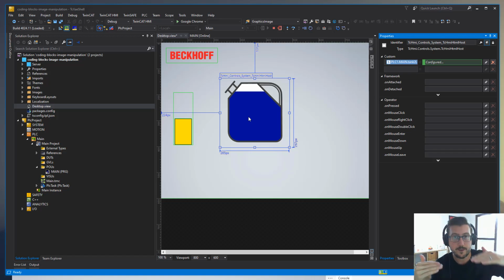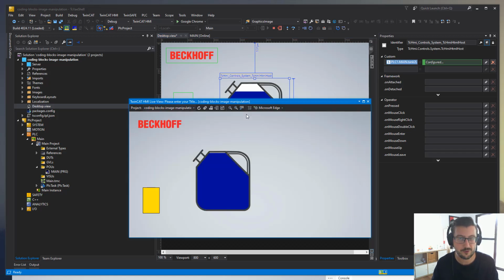And when I start adding values to it, it starts making its way down to a value of around about 280. Now that corresponds to how big the scalable vector graphic is at its core, not as I've drawn it here, but when the graphic was created, that number is fundamental to it. So you would have to do some scaling. You can either do scaling inside here, or you can do scaling in the PLC. So wherever you feel it's right. In this instance, I'm going to do the scaling in the PLC, so I can just drive the values.